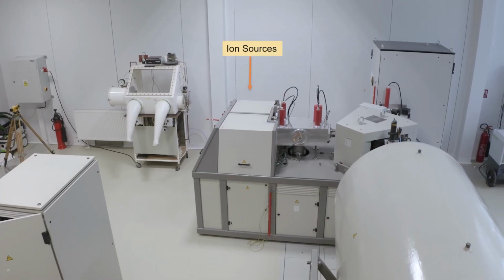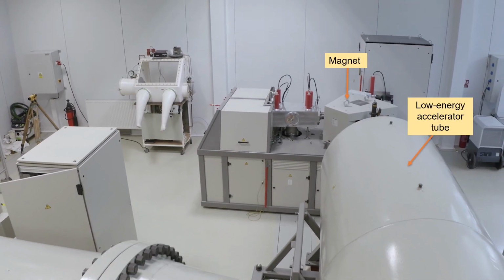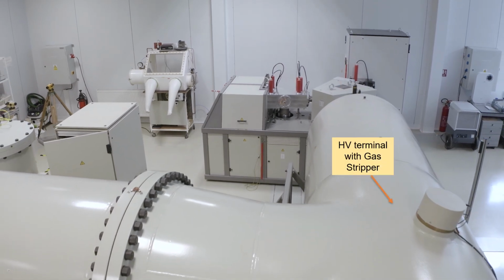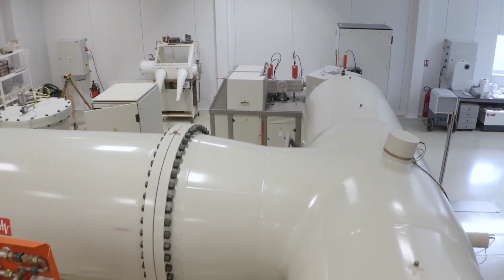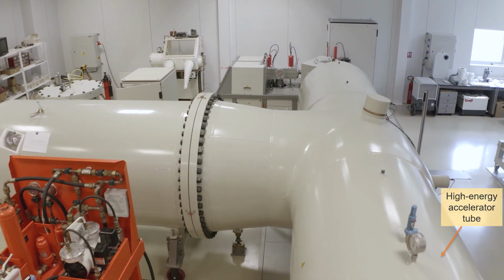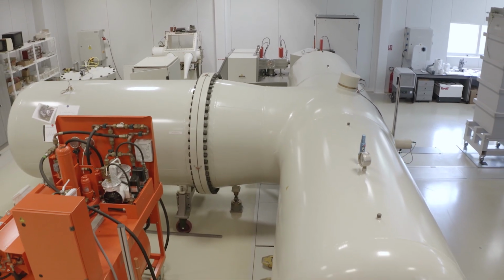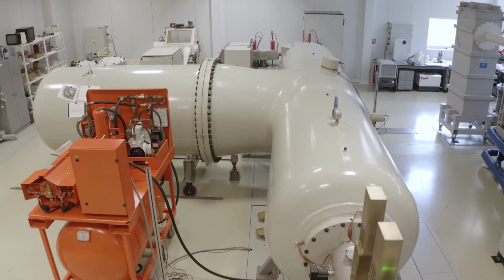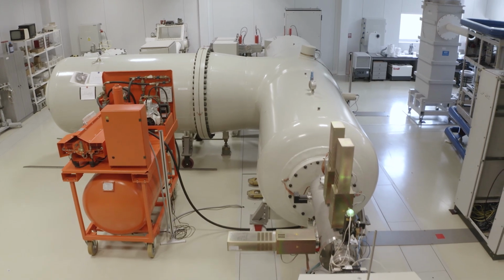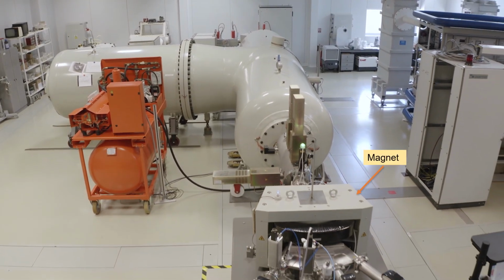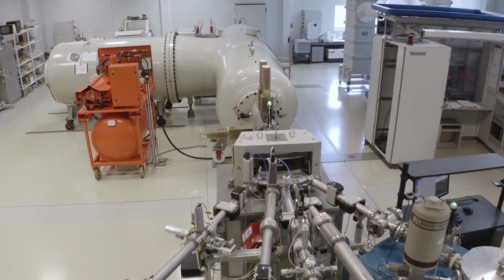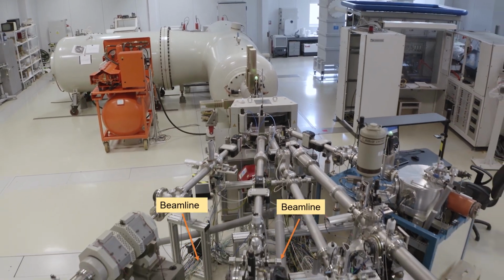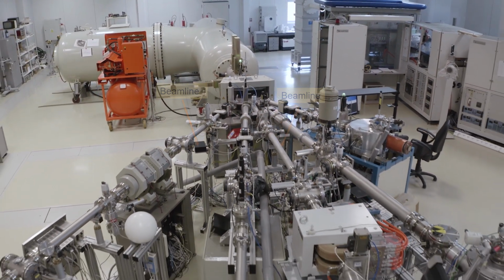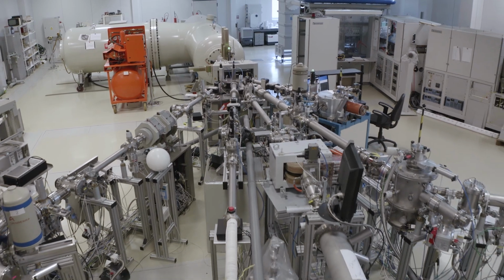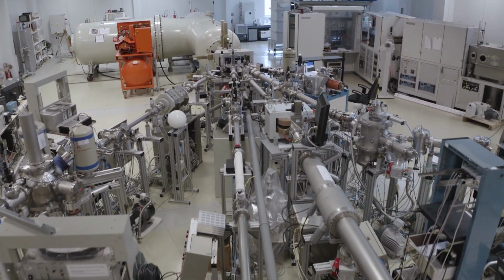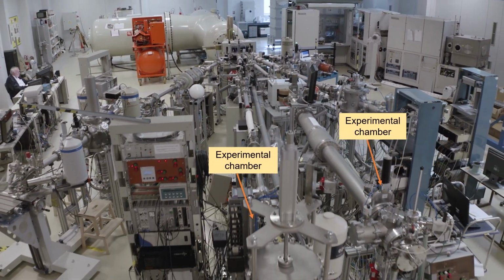Tandetron is used for production of ion beams with energies in the range from 400 keV to 30 MeV of almost all elements of the periodic system. The produced ions are used for the ion beam analytical methods and for modification of solids properties. It is the medium current version with a terminal voltage varying from 200 kV to 3 MV. The accelerator is equipped with 3 ion sources, which are electrically isolated from the accelerator and operate at a voltage of 20 kV.